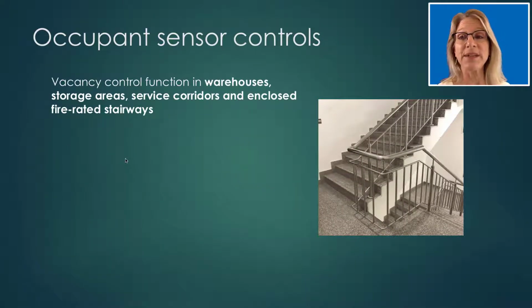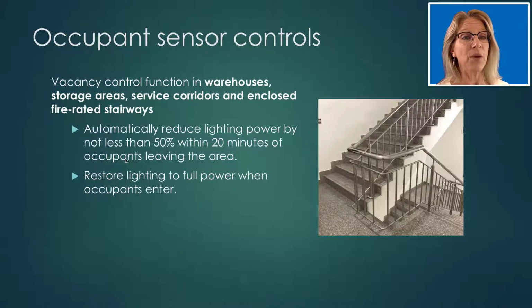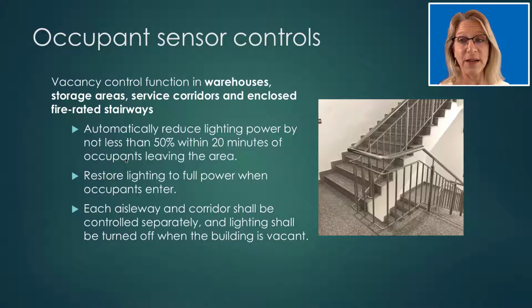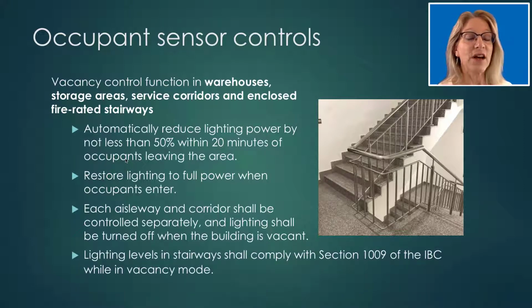Now let's go through some of the occupant sensor control requirements for specific space types. For warehouses, storage areas, service corridors, and enclosed fire-rated stairways, vacancy controls are required to automatically reduce the lighting power by not less than 50% within 20 minutes of the occupants leaving the area, and they're required to restore the lighting to full power when the occupants re-enter. Aisleways and corridors shall be controlled separately, and the lighting in these areas shall be turned off when the building is vacant. And also note that these requirements do not supersede the egress lighting requirements in section 1009 of the IBC, particularly for stairways.